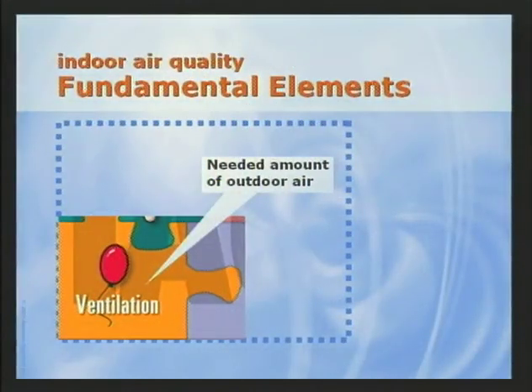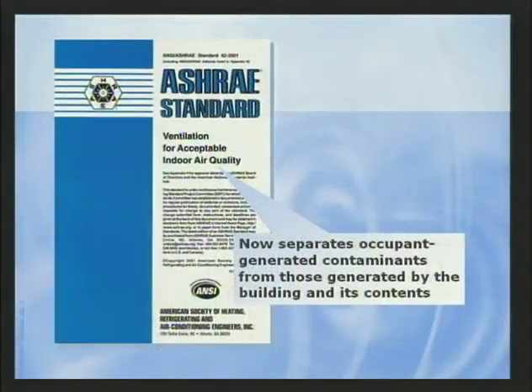How much outdoor air is needed in various school spaces? ASHRAE Standard 62, through the continuous maintenance process, is changing the requirements for ventilation system design for classrooms. Historically, most designers have used the ventilation rate procedure to determine the amount of outdoor air required in spaces. This prescriptive procedure has been changed significantly by Addenda 62N, which was approved for publication by the ASHRAE Board of Directors in early summer 2003. It is expected to be published on the ASHRAE website by January 2004. Let's take a look at what's changed.